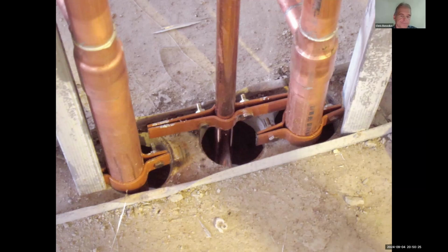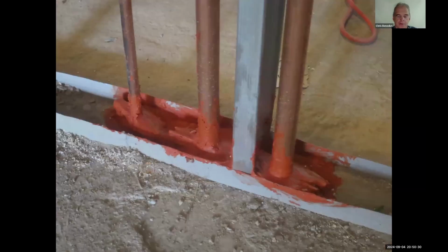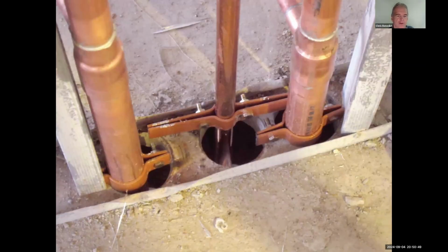There are code-approved details to fireproof around where the pipe goes through the floor-ceiling assembly. This is fire caulk. It's like $500 for a 5-gallon bucket. It's expensive stuff. And you can goop it on there, and you have to put some mineral wool in there. They sell special sleeves and all, but when you have a huge hole like this, it's so much caulk and it's not going to work well.